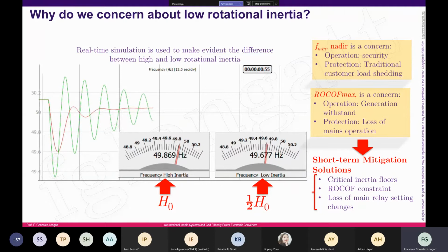But if you look, we also have more oscillations when we reduce the rotational inertia. Those oscillations in frequency have many consequences, especially for the mechanical components related to generation. This is critical—we can start to break shafts, break blades, and damage many other components.